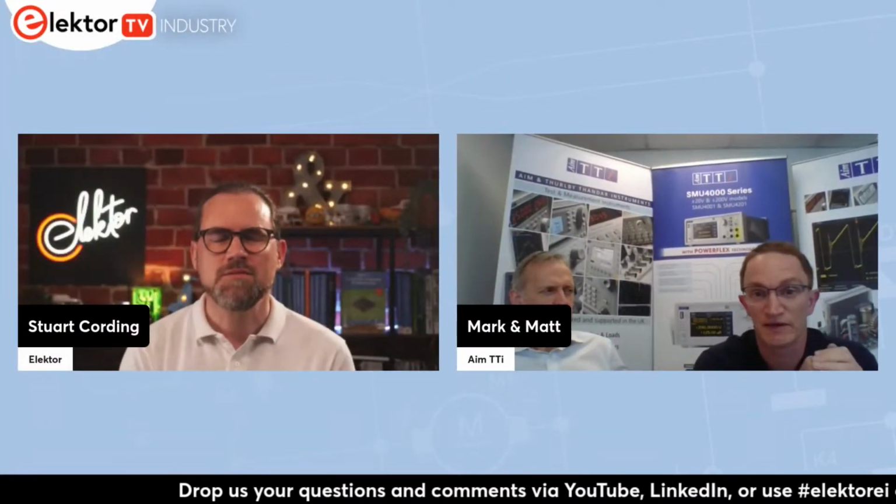But we're very proud that we've managed to get the voltage range down to 20 millivolts and the current range down to 200 nanoamps. And we've tried to offer many other additional benefits, such as guarding on the rear terminals. We've added 2-wire plus guard on the front terminals. So if you want guarding on the front terminals, when you select the 2-wire plus guard, the high sense terminal becomes a guard terminal.